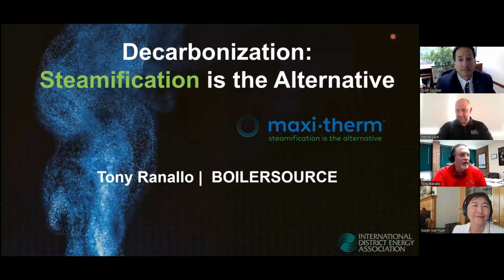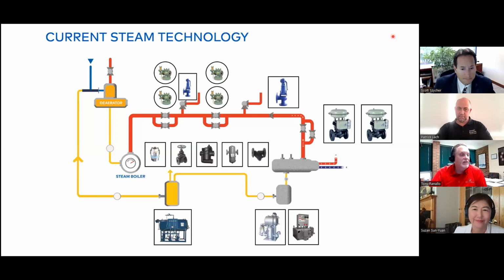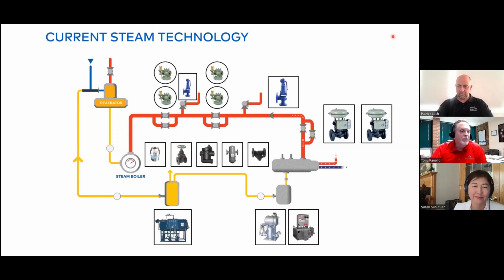Welcome, everybody. And let's jump right into it. We're going to start off by looking at the current state of steam technology today. This is a pretty typical illustration of what a steam system would look like. As you can see over here, we've got our typical deaerator, boiler, we've got PRV stations, 1/3, 2/3 valves with relief valves and two drops here, maybe a first stage and a second stage pressure drop.